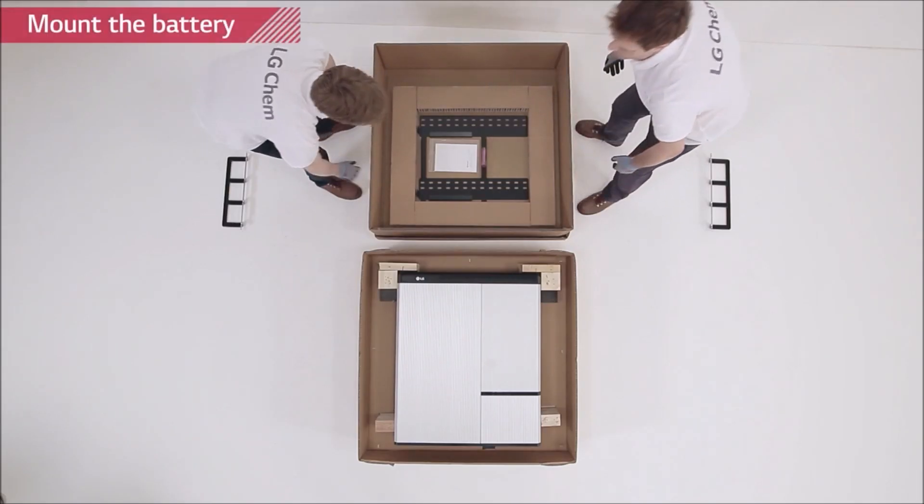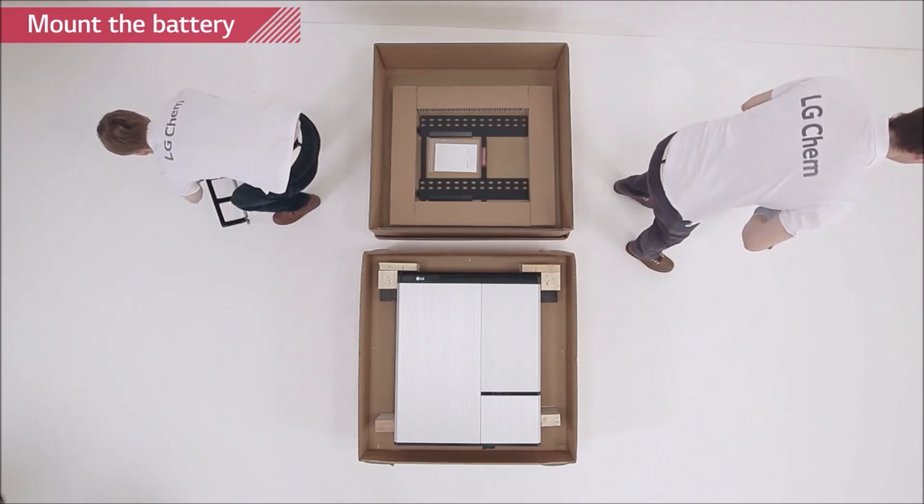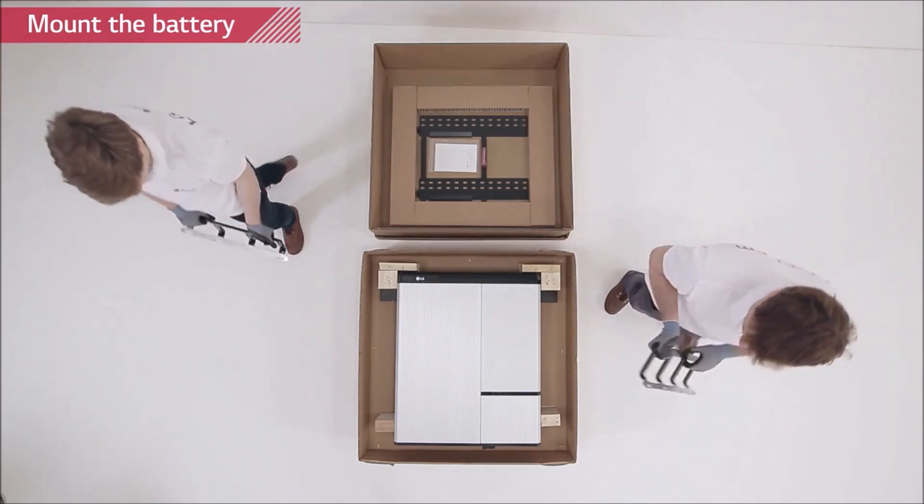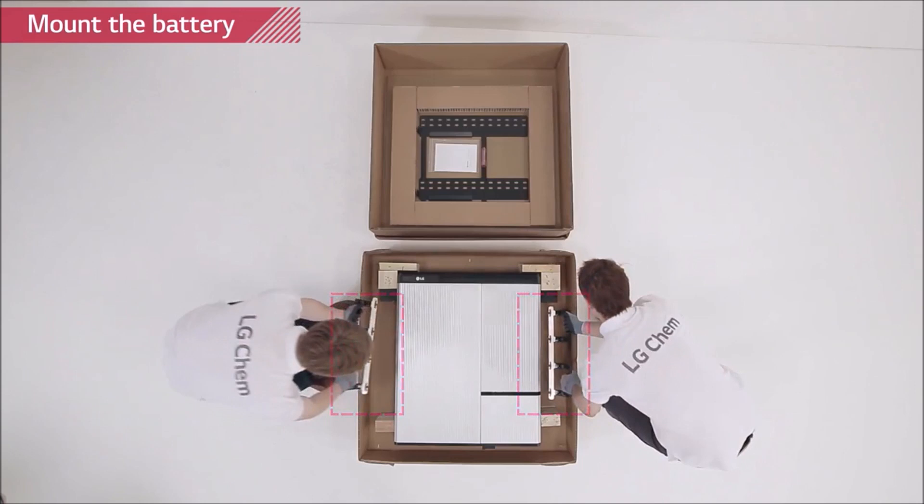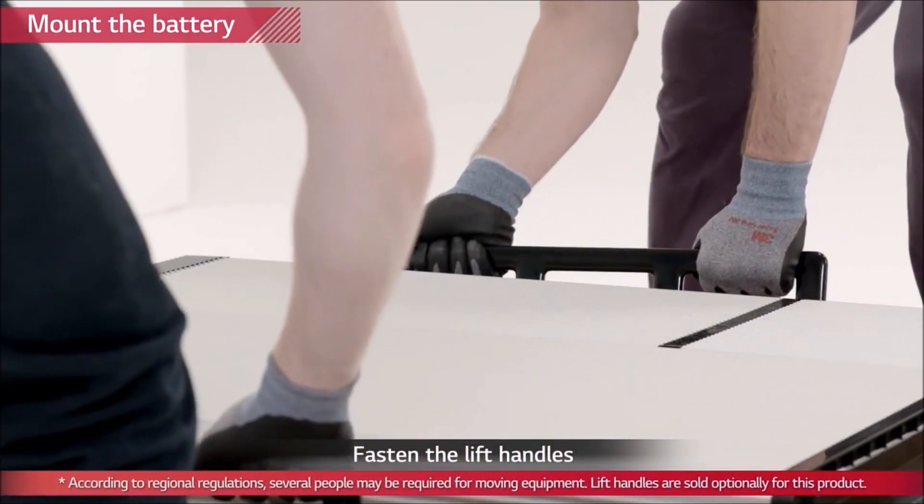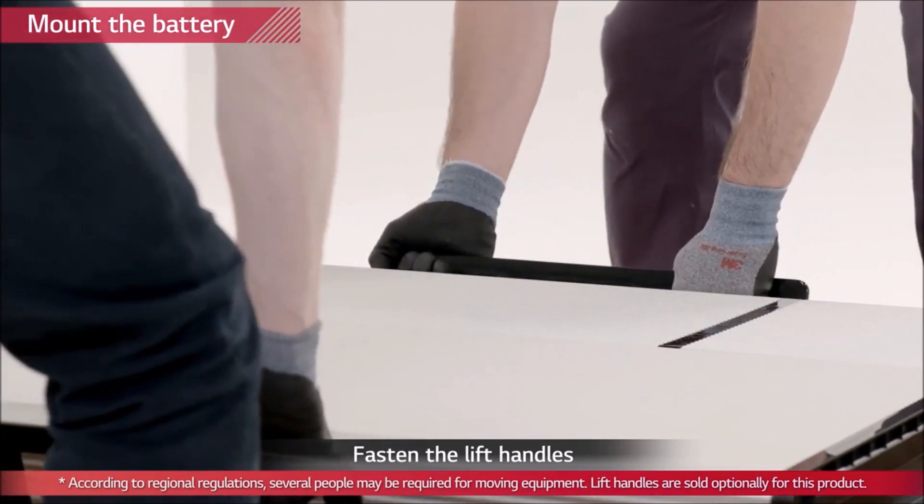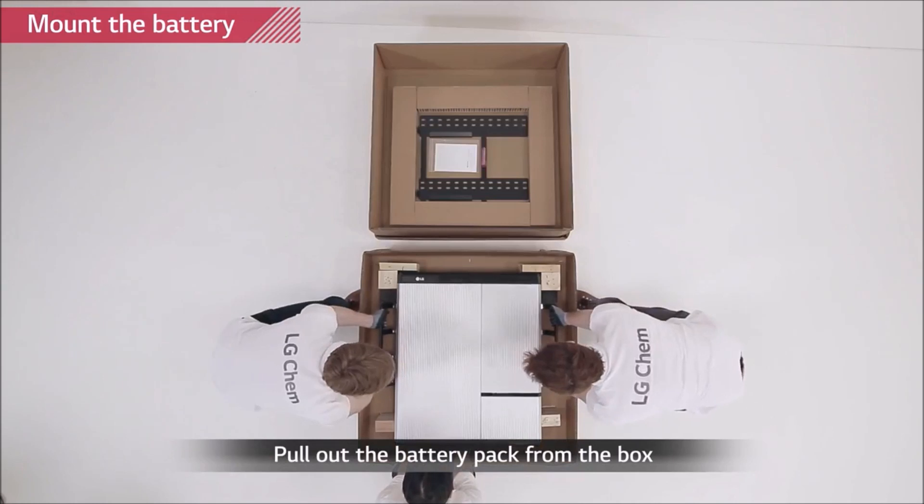Attach the lifting handles to the hex socket screws located at the back of both sides of the RESU pack. Lift the battery pack using the handles. Handle the RESU 10H carefully as it weighs about 100 kilograms. Note that the wall on which the battery pack will be mounted has a capability to support weight over 150 kilograms.